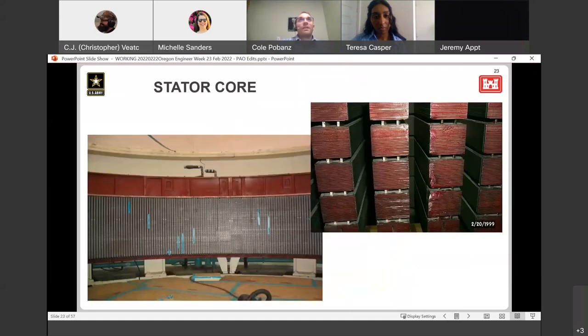The stator core is made up of thousands of laminated metal sheets. In the picture on the right, you can see these corners got burned a little bit. This is really bad and means they need to be replaced, which involves restacking that entire section of tiny metal sheets. You have to wear special gloves so you don't get cut, because they're super thin. It's lots of work and very expensive.